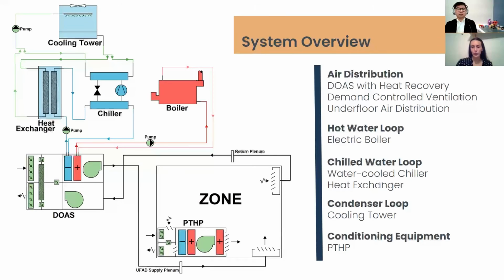An electric boiler was chosen in order to keep the HVAC system completely powered by electricity and in turn by renewable hydropower. This was possible since the boiler only serves the DOAS, which does not require a high capacity, which is often the limitation for electric boilers. The water-cooled chiller was paired with a heat exchanger and a cooling tower. The water-cooled chiller was shown to be more efficient than an air-cooled chiller when simulated in EnergyPlus. Since the building is located in Quebec, there is an abundance of water, and a water-cooled chiller can be considered an appropriate choice as the cooling system.